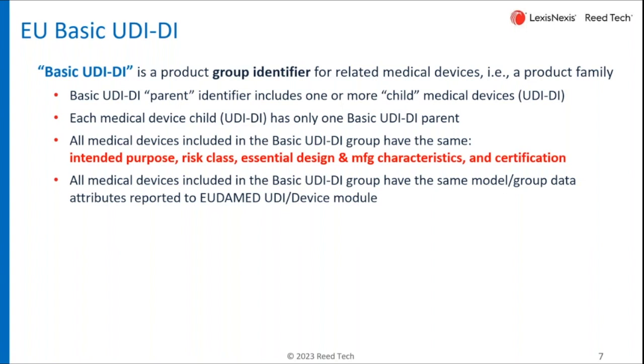This Basic UDI-DI is simply a group identifier for very similar medical devices — like a family name, if you will. That particular identifier, we'll call it a parent, has to have at least one child. So when you identify a Basic UDI-DI, it does have to have one device connected to it.